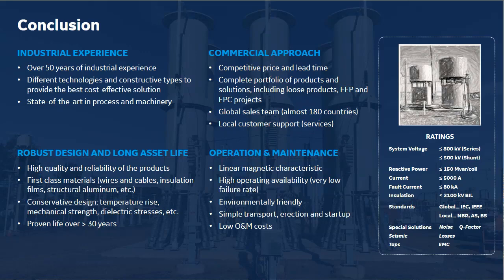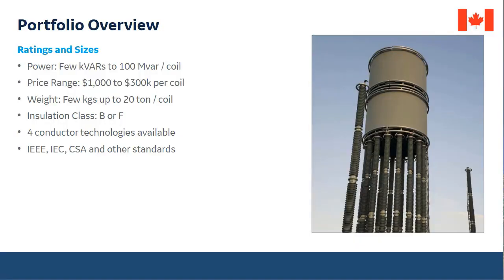One more question. Can we use air core reactors for smoothing reactors in HVDC? The answer is yes. And actually, in one of the pictures that we had, this one, this is showing a smoothing reactor. I'm not sure about the voltage level, but maybe 300, 400 kV continuous DC. And yes, they can be used for smoothing in HVDC at extremely high voltage levels. And yes, they are used for smoothing application. This is a site in Canada, a very special application.